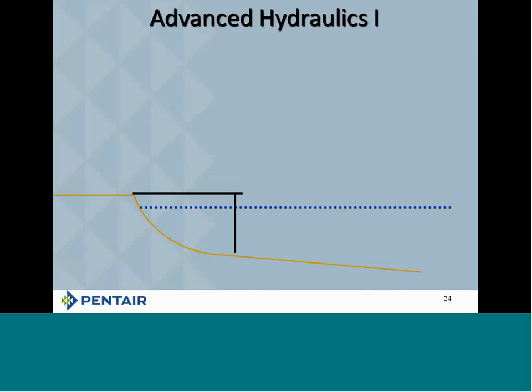All right? Now, we're going to talk two things here. We're going to talk suction lift, how to calculate total suction lift, and of course, how to calculate friction loss. So what we've got here is a customer who's got a pump sitting on the end of a pier. He's got some pipe leading down into that water. That pipe happens to be 10 foot in length. Now that's overall linear feet of pipe is what we're looking at.